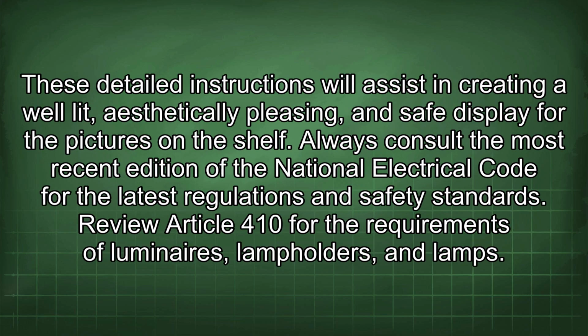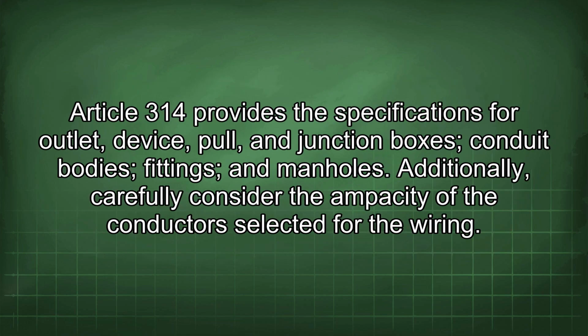These detailed instructions will assist in creating a well-lit, aesthetically pleasing, and safe display for the pictures on the shelf. Always consult the most recent edition of the National Electrical Code for the latest regulations and safety standards. Review Article 410 for the requirements of luminaires, lamp holders, and lamps. Article 314 provides the specifications for outlet, device, pull, and junction boxes, conduit bodies, fittings, and manholes. Additionally, carefully consider the ampacity of the conductors selected for the wiring.